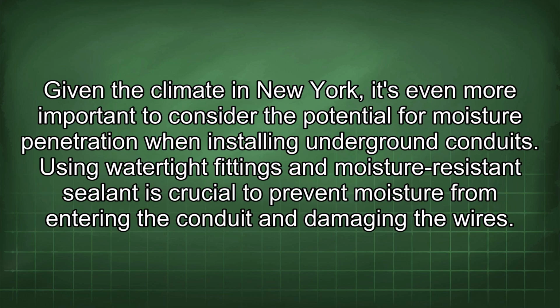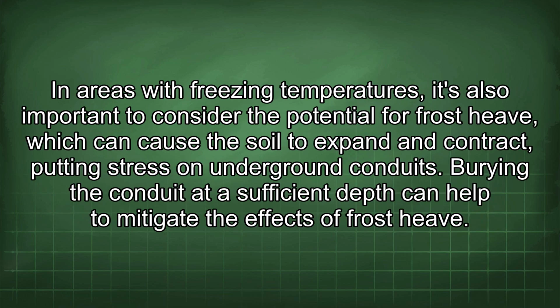Given the climate in New York, it's even more important to consider the potential for moisture penetration when installing underground conduits. Using watertight fittings and moisture-resistant sealant is crucial to prevent moisture from entering the conduit and damaging the wires. In areas with freezing temperatures, it's also important to consider the potential for frost heave, which can cause the soil to expand and contract, putting stress on underground conduits. Burying the conduit at a sufficient depth can help to mitigate the effects of frost heave.